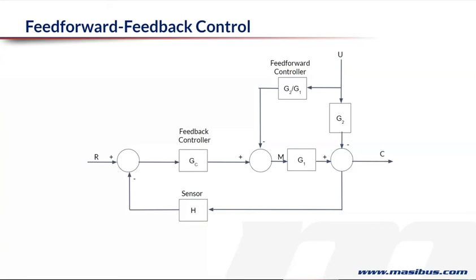To some extent we know, I had given an equation on that basis. We could calculate what is the flow effect on the outlet temperature. So if I change my flow by some kg per second, it will change the temperature say by 2 degrees. So I can put that approximation in that feed forward controller here, right?